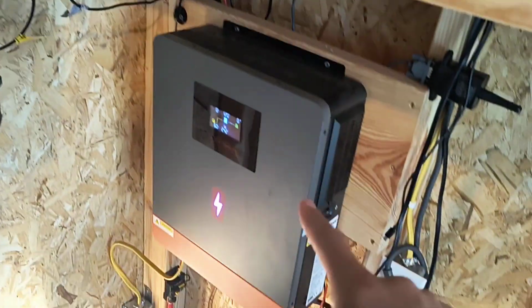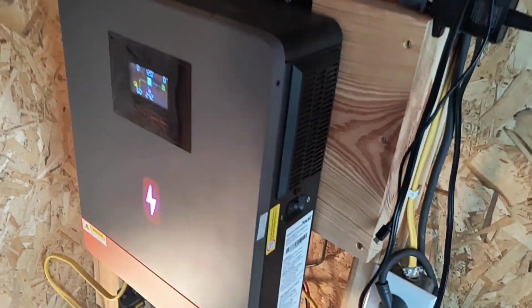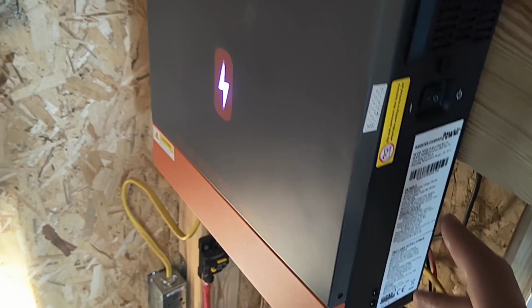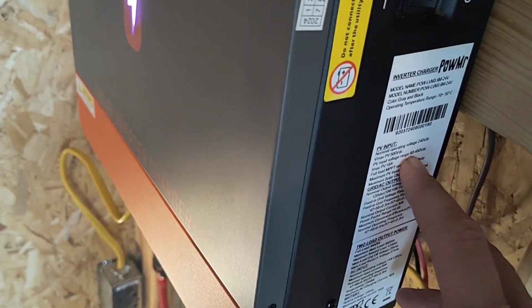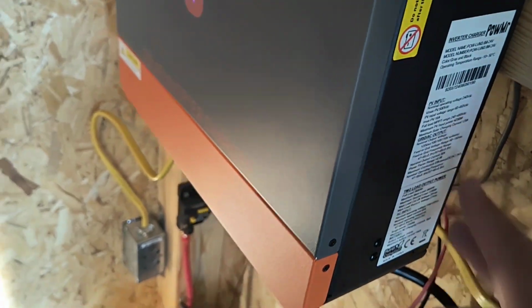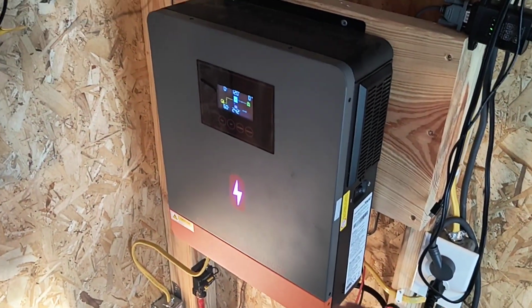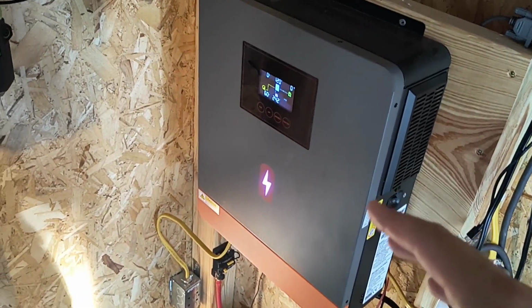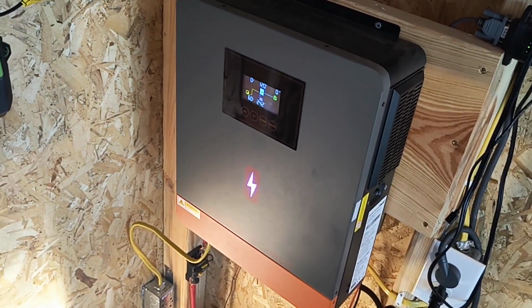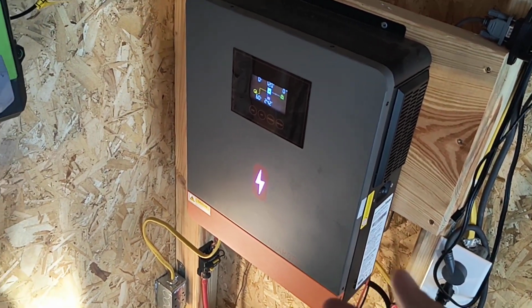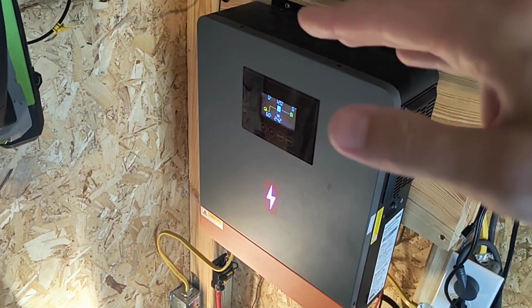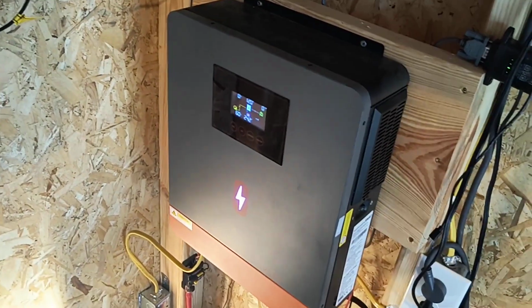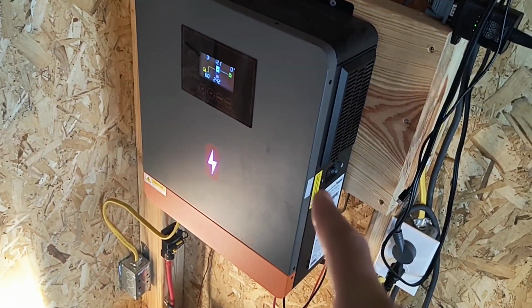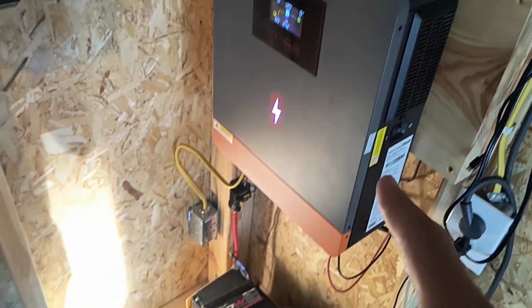The problem right now with the PowMR is that its voltage is a little too low for it. The specs for the PowMR are 60 to 450 volts, but they do recommend being kind of in the middle, and I'm right at the bottom of the MPPT range. The production isn't where it needs to be, because right now I'm getting about 300 watts during the day, and it constantly drops out then comes back. It'll go down to 0 and then come back. I think it's just a little too low for the MPPT built into this, so I am going to replace it with the Victron.